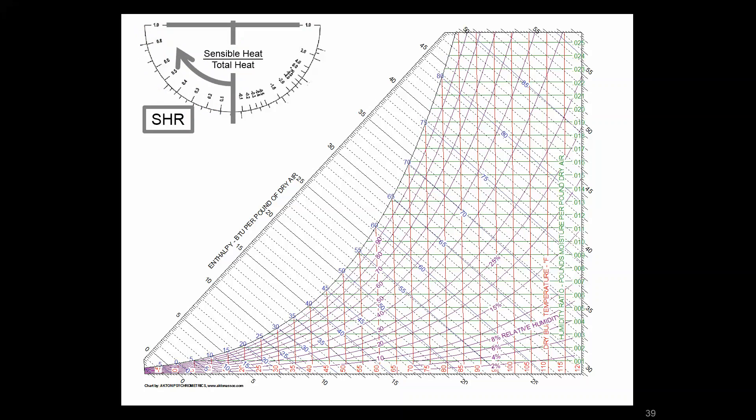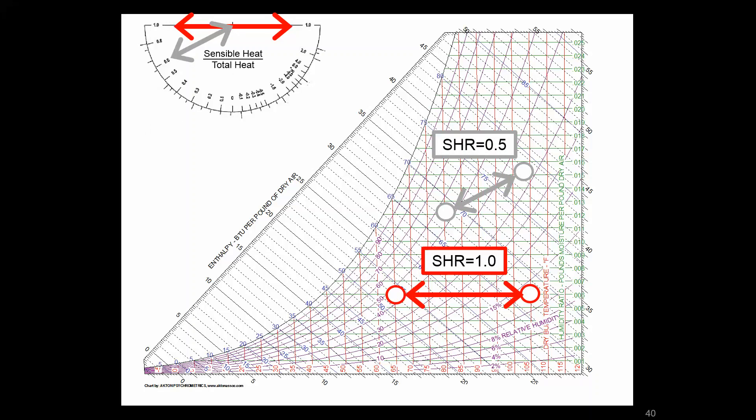Another way we talk about not just states but processes is with things like the sensible heat ratio. Sometimes in psych charts you might get a wheel at the top here or lines on the outside that say SHR. We're talking about the sensible heat as a ratio of the total heat, which tells you how much latent energy versus sensible energy is going into that process. You line up the angle of your process and match it with this wheel. We can talk in terms of a sensible heat ratio of 0.5 versus this flat one of 1.0, which tells you all of the process is characterizing sensible heat change.